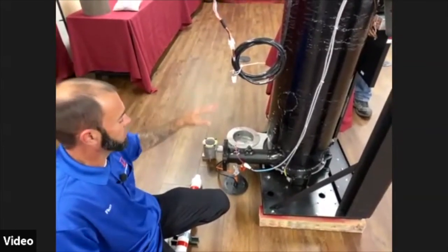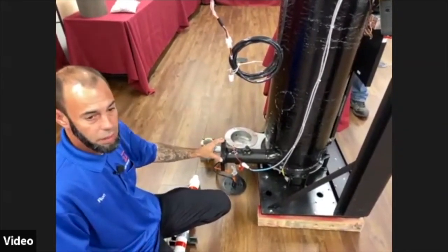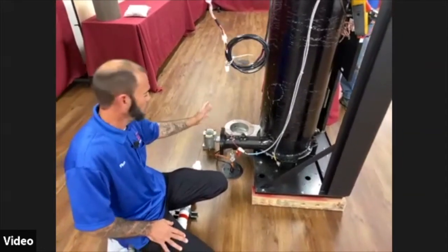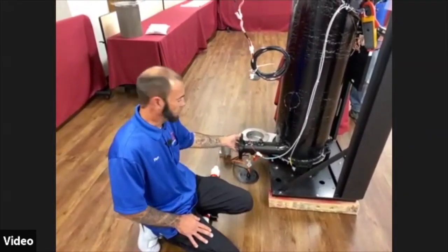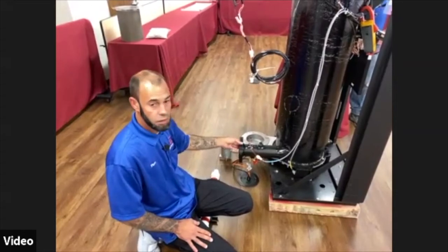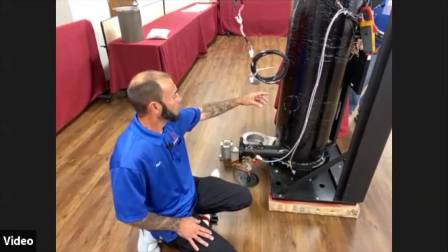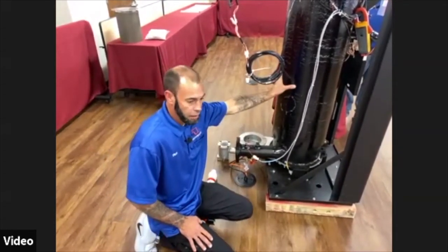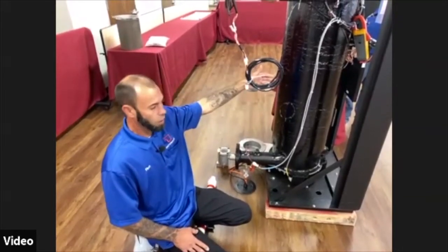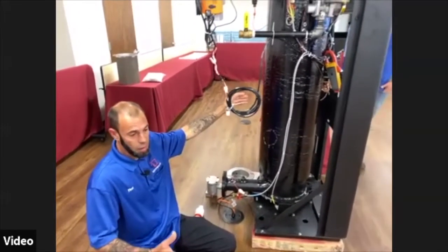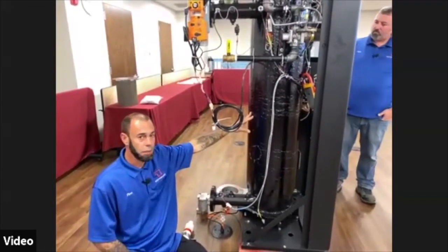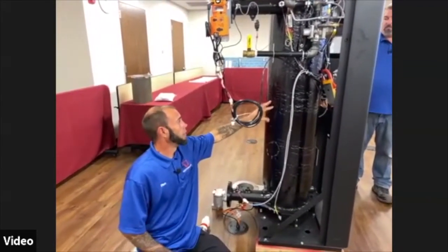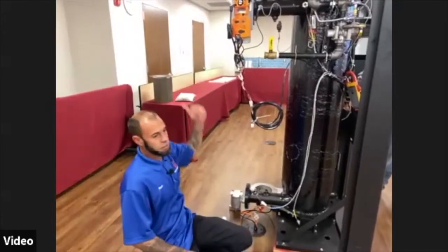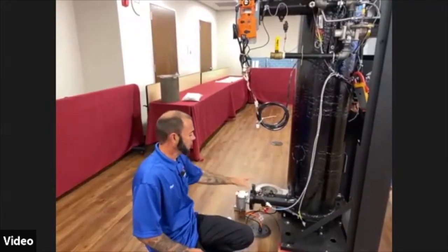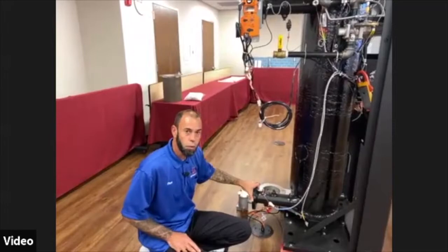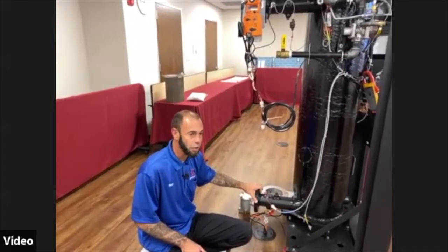And what this would be designed for would be a situation where we may have multiple temperatures. We would bring our low temp into the bottom inlet so that it gets full condensing. And then it basically is preheated by our midsection, or our second return that comes in. That might be, let's just call it, the building loop. And maybe that's 140, and then we go back out to the system from there mixed. So it allows us full condensing capabilities and higher efficiency ratings.